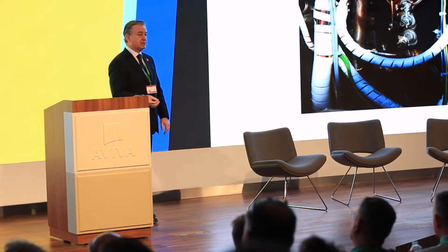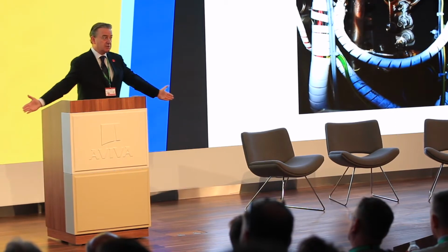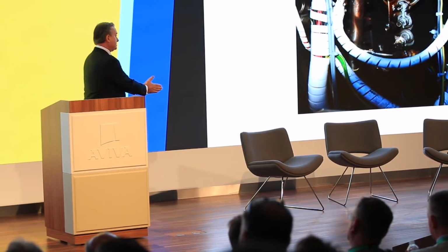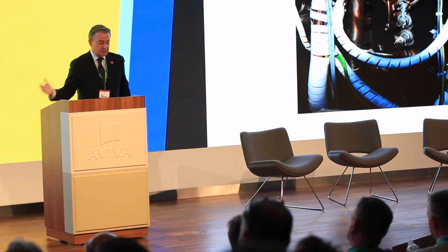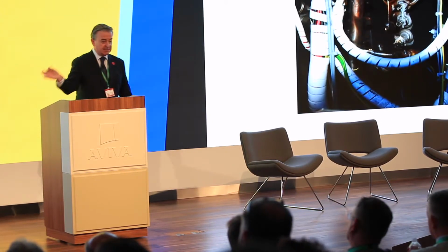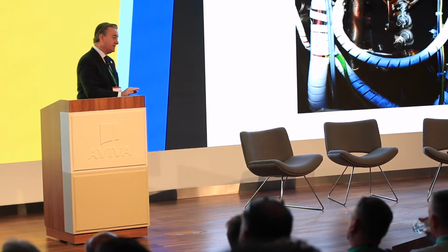Secondly, it signalled the house fire alarm system, which in turn signalled the fire brigade. It shut the automatic doors in the room where the sterilisation machines were, shut down the air conditioning, signalled the BMS system, and released the Firepro all at the same time.